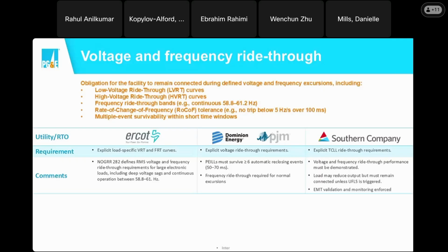Like in AEP, you don't commonly find 3-shot reclosing, you find 2-shot reclosing. So in their requirements, you'll see it written as: if you consider the double reclosing shot, then 4 automatic reclosing events. But if you look at Dominion, where they have 3 reclosing shots, then it's going to be 6 automatic reclosing events. So you see some of these nuances play out - again, telling you all this is very system specific.